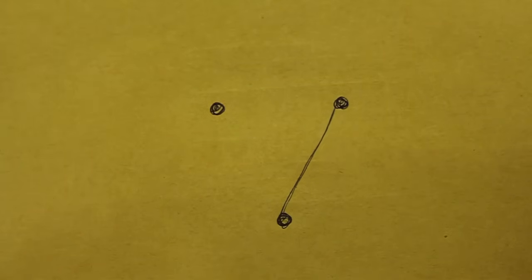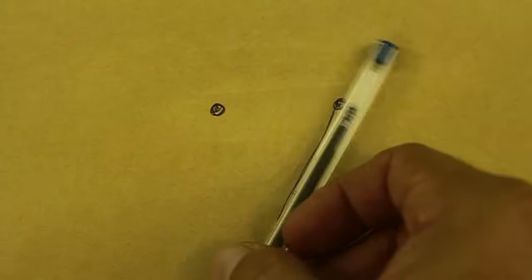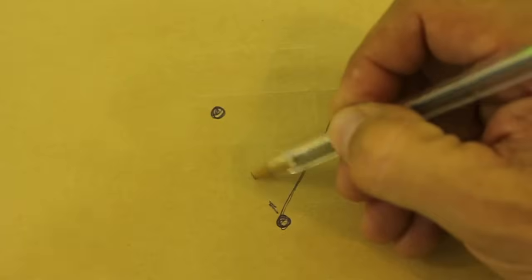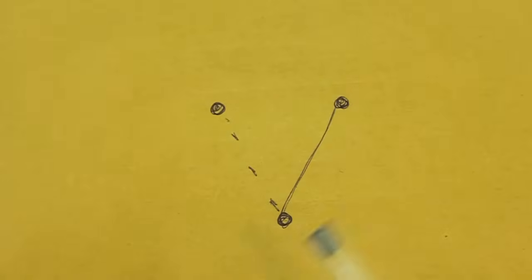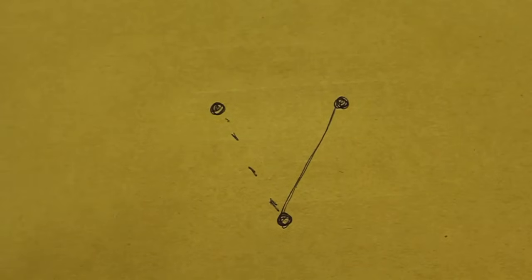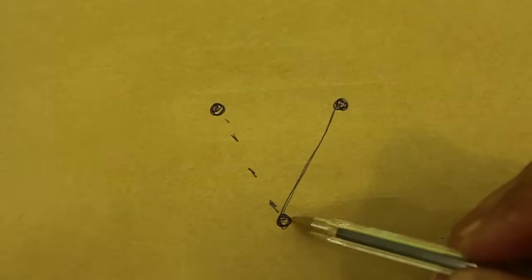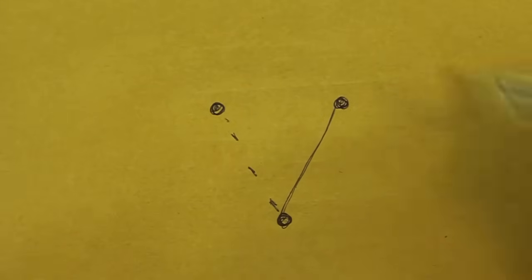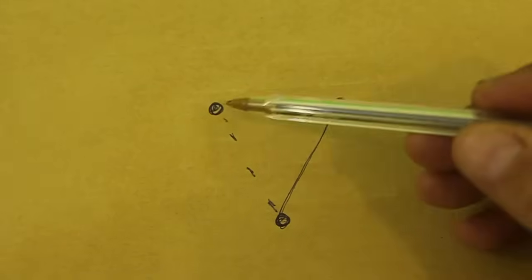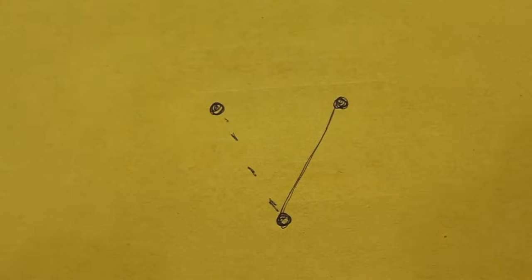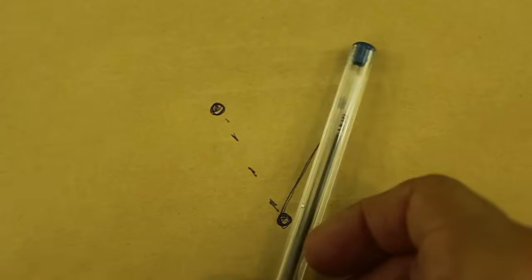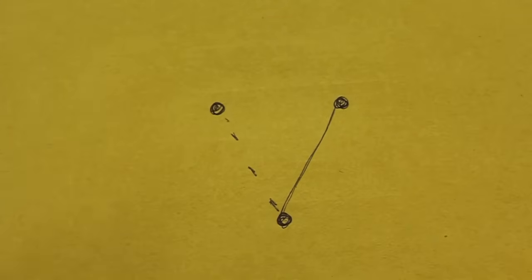When we energize the coil, this moves to the other position and now we have a connection here and not here. So when we check with the multimeter, we will see continuity between these two and not between these two. And when we energize the coil, the situation changes to the other way.